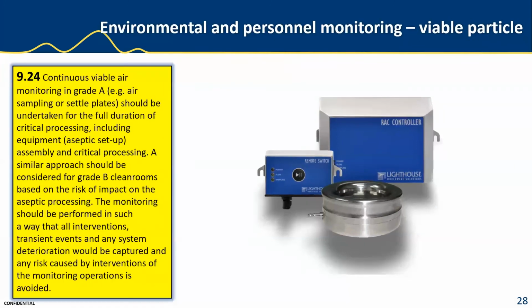Now we talk about continuous viable air monitoring. So 9.24, continuous viable air monitoring in grade A, for example air sampling or settle plates, should be undertaken for the full duration of critical processing, including equipment, aseptic setup, assembly, and critical processing. A similar approach should be considered for grade B clean rooms based on the risk of impact on the aseptic processing. The monitoring should be performed in such a way that all interventions, transient events, and any system deterioration will be captured, and any risk caused by interventions of the monitoring operations is avoided.